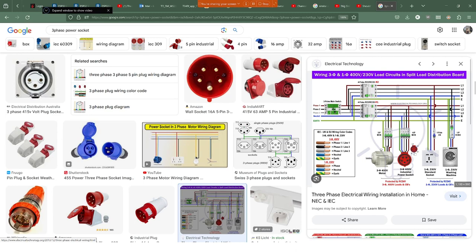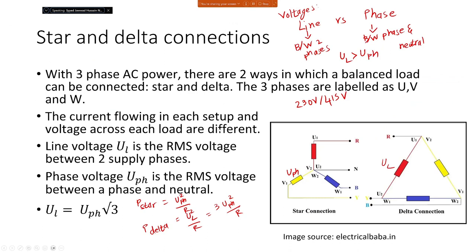But for motors, you're going to need three phases. So they're giving line voltage here, which is root 3 times the supply voltage. So if you multiply 230 with 1.732, which is root 3, you get 398, which is 400 volts. So that's why they say 400/230. Okay. So some real life thing, not 415. I thought it was 415. Okay, can't remove it. Fine.